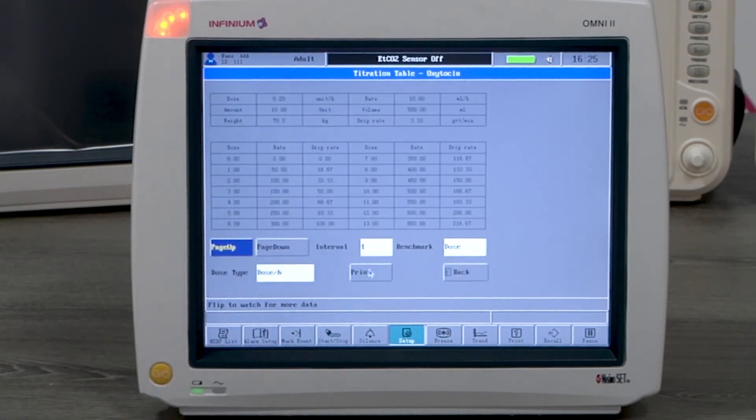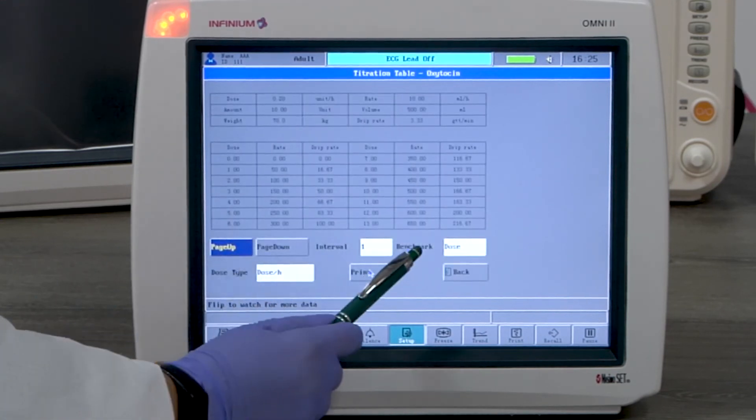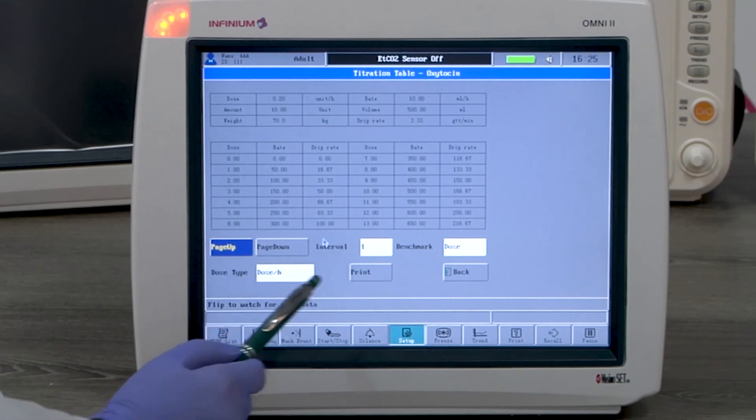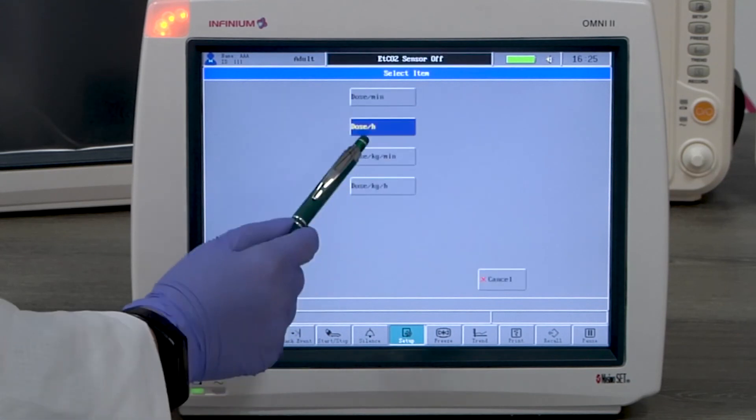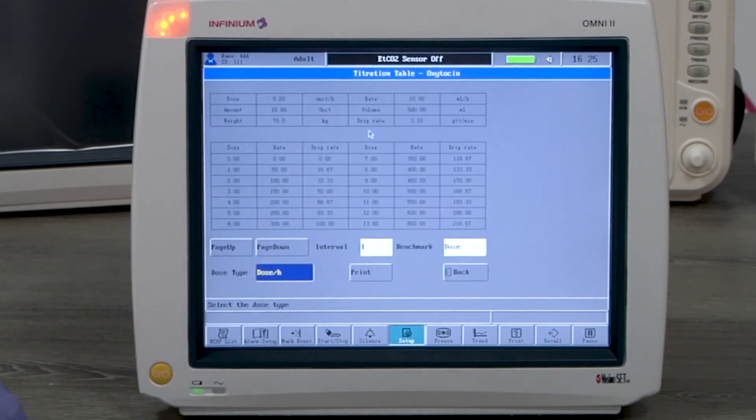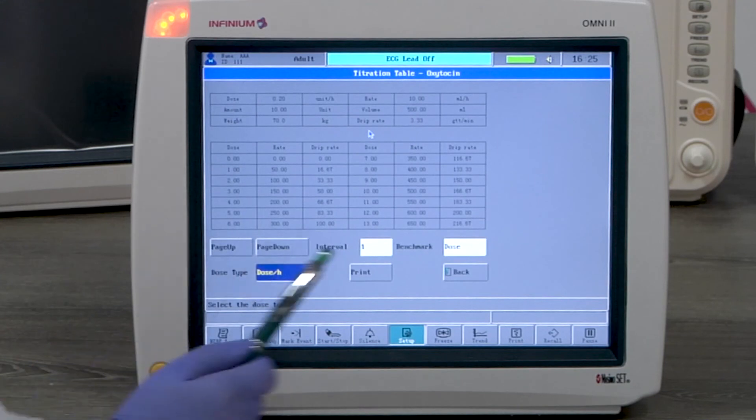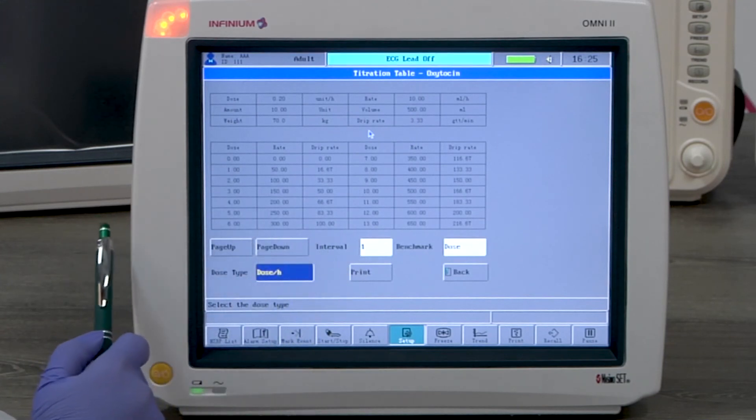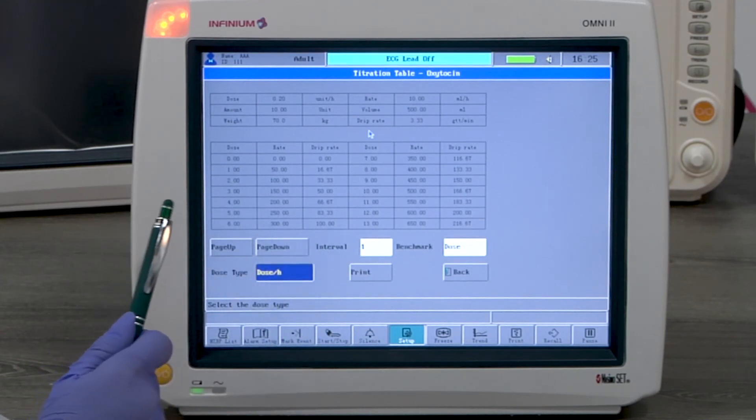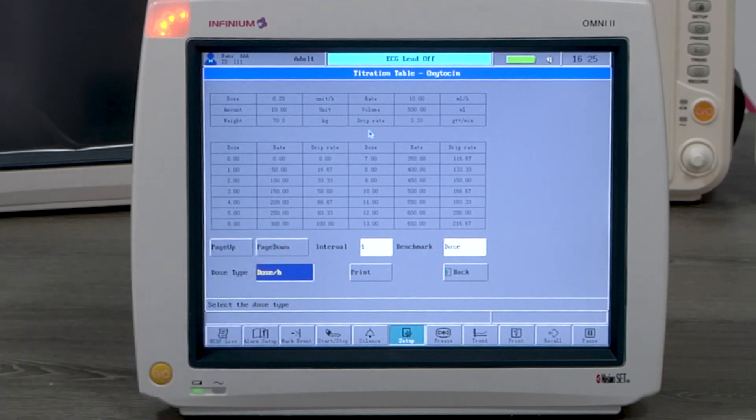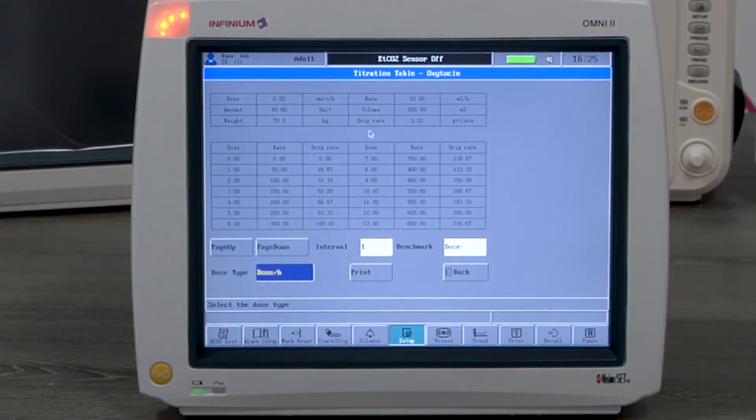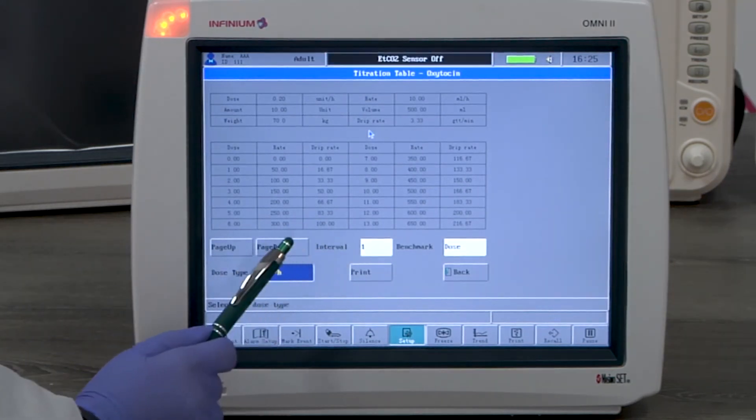Once the numbers are input, you can go to titration table. Here you can select the benchmark, the interval, and the dose type. We have selected dose type as dose per hour. This chart lists the value of rate and drip rate under different dosages per hour. Select page down to see more results.